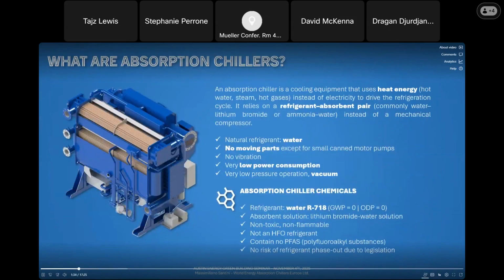So what exactly is an absorption chiller? Unlike traditional chillers that use electric compressors, absorption chillers use heat energy, such as hot water, steam, or hot gases, to drive the cooling cycle. They use the most natural refrigerant, water, and have no moving parts, no vibration, very low power consumption, and work under vacuum condition. In the absorption chiller, in addition to water as refrigerant, we use lithium bromide as absorbent solution. We have a GWP of 0 and an ODP of 0. The chemicals are non-toxic, non-flammable. The refrigerant is not an HFO.